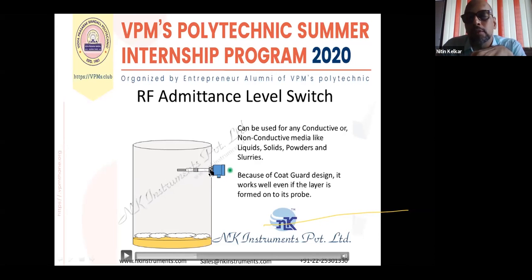Because there is a current in the earlier stage when this was not there, conductivity level switch, this high to low, which is reference, the current passes and the switch operates. But here there is one more probe which is equipotential, and some layer is formed onto it. Now the current will not pass from this to this through that layer, because both are at equal level.